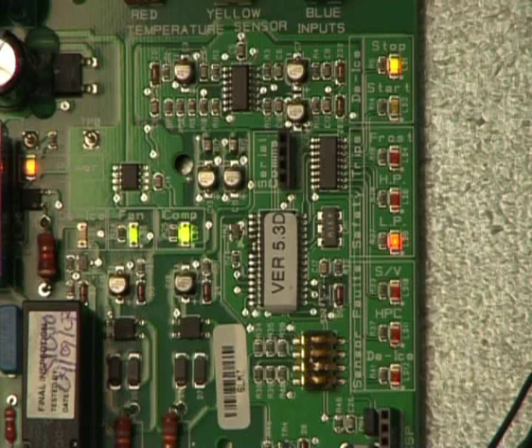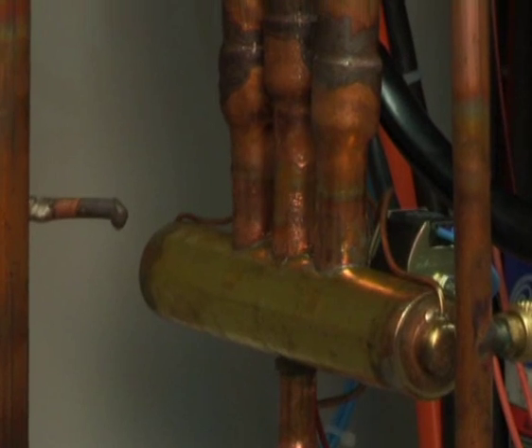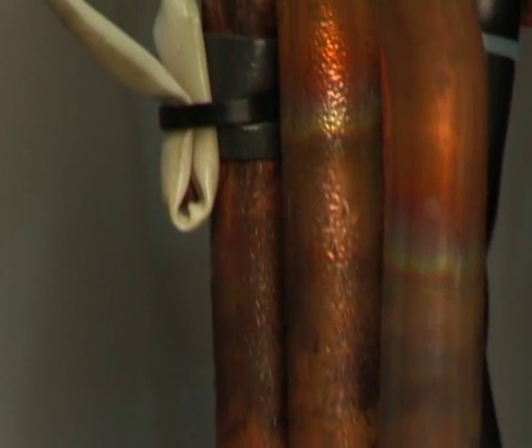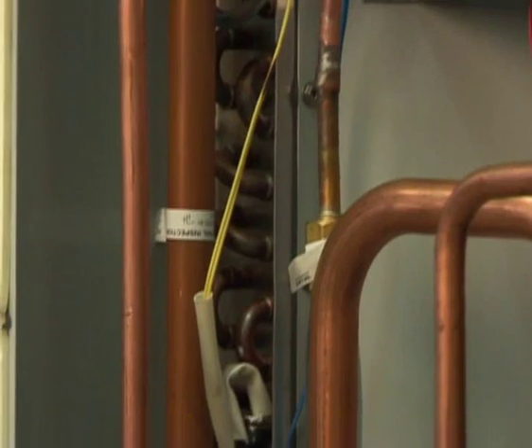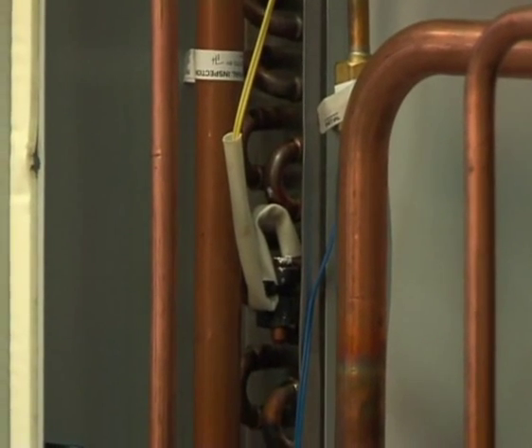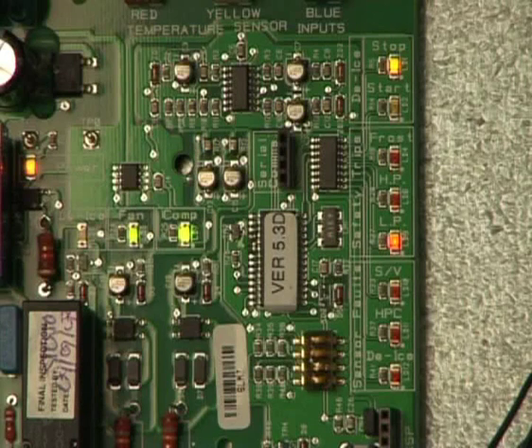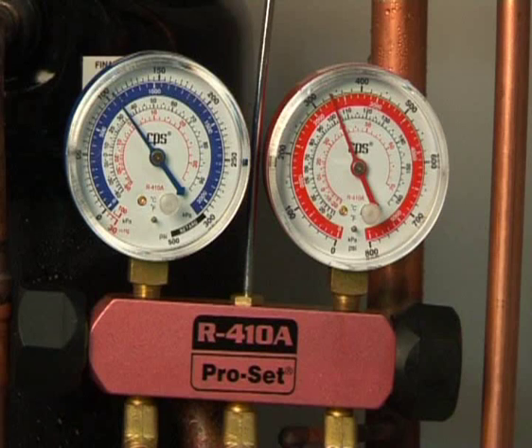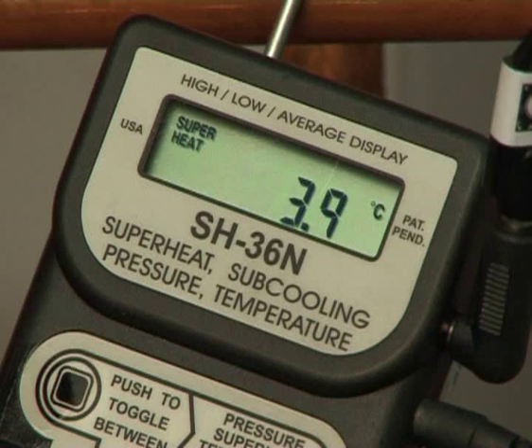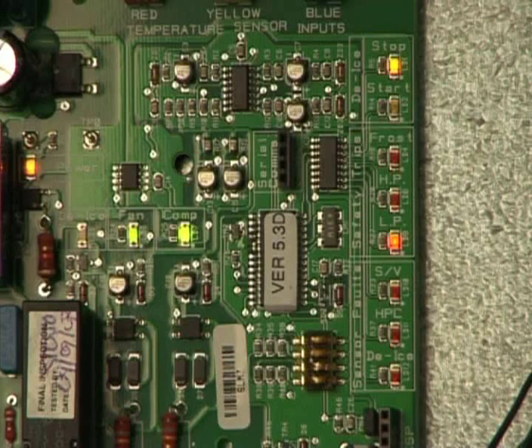However, a more accurate method of detecting refrigerant loss or shortage has been designed into the OUC. On the cooling cycle, the temperature at the service valve, which is on the suction side, is compared to the temperature of the HP sensor, and should there be insufficient temperature difference, indicating loss or shortage of refrigerant, then a fault is indicated via the LP LED, and the compressor will be shut down temporarily. The most likely cause of an LP trip will be high superheat. Temperzone recommend a system superheat of between 3 to 5 degrees C.